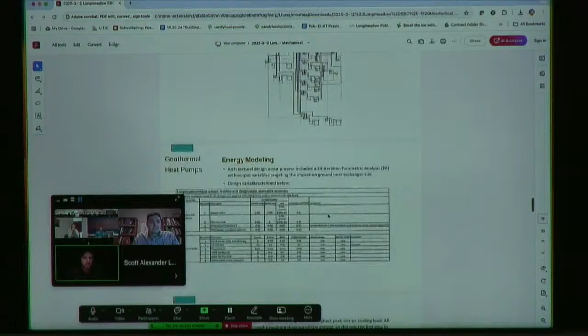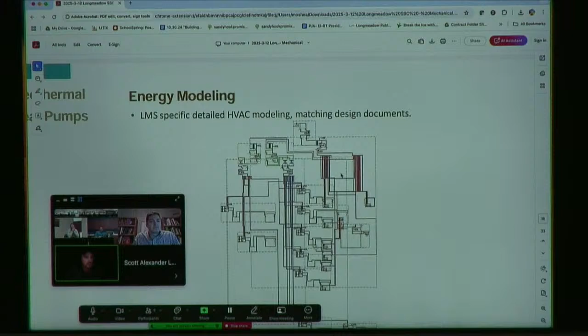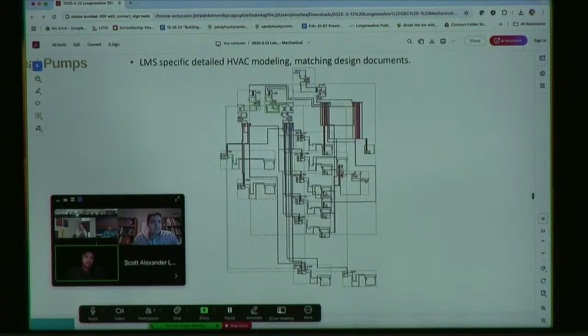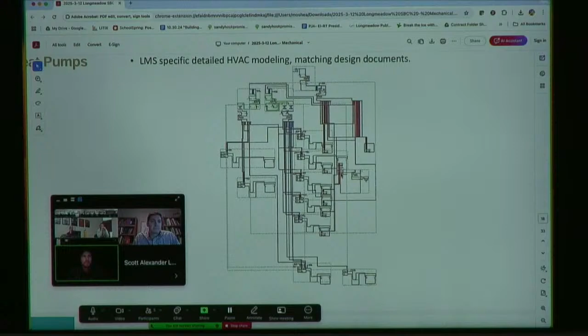One thing to note at the top of that slide is that I currently don't have a ground heat exchanger object shown, because we're in the process of sizing that. Instead I have district objects, which act as load gobblers. Depending on the architectural configuration we're varying right now, the load to the ground changes. The rest of the mechanical system is fixed throughout the design assist process, but we are examining how it impacts the loads on the ground.